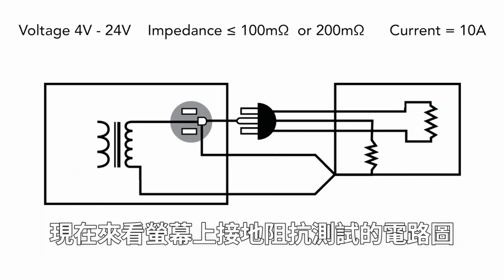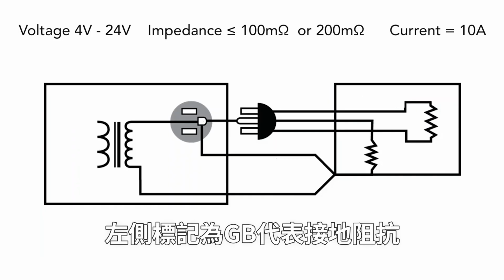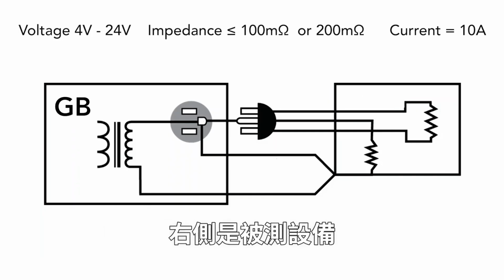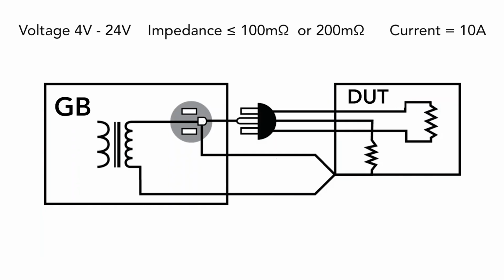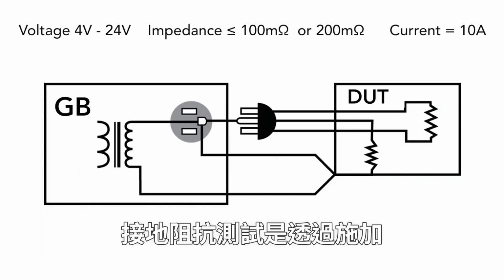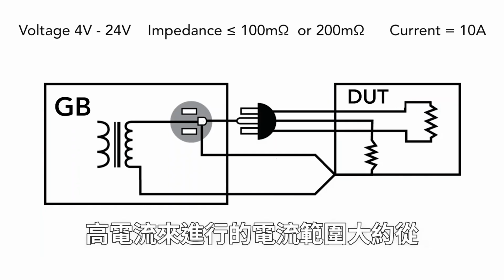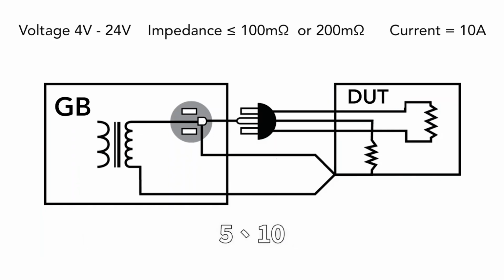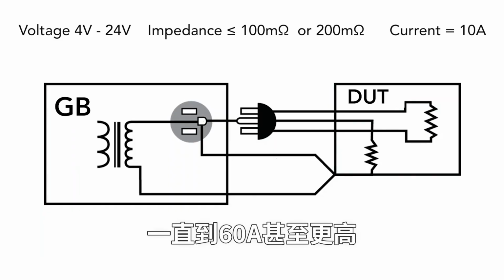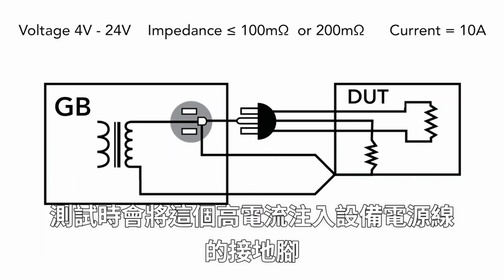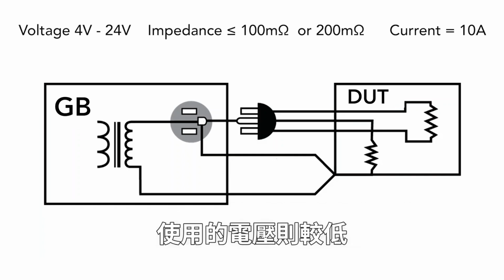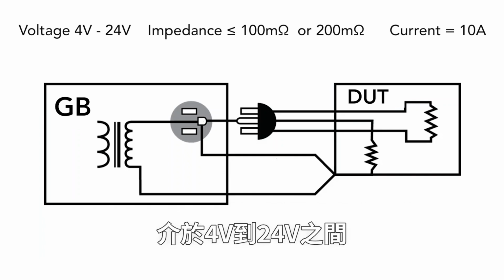So looking at the circuit for the ground bond test, on the screen the left side is labeled as GB for ground bond, and the right side is the device under test. When the ground bond test is performed, high current in the range of anywhere between 5, 10, 15, 20, all the way up to 60 amps or even more is injected into the ground pin of the device's power cord at a low voltage anywhere between 4 to 24 volts.